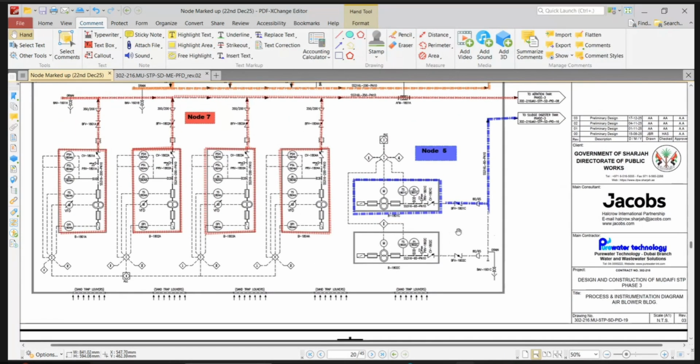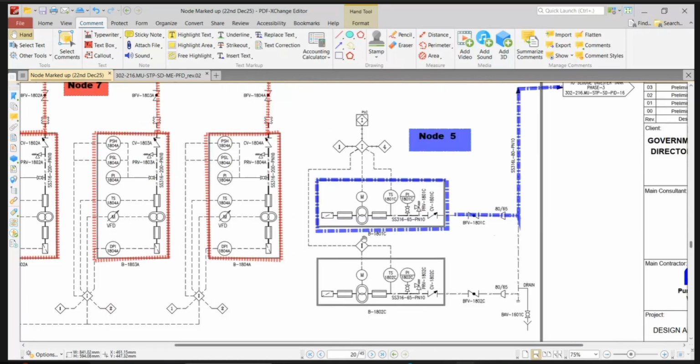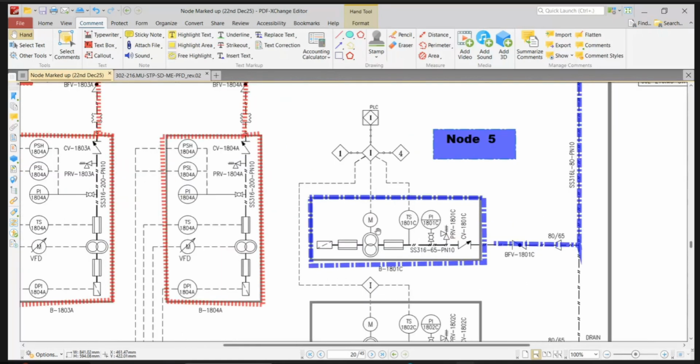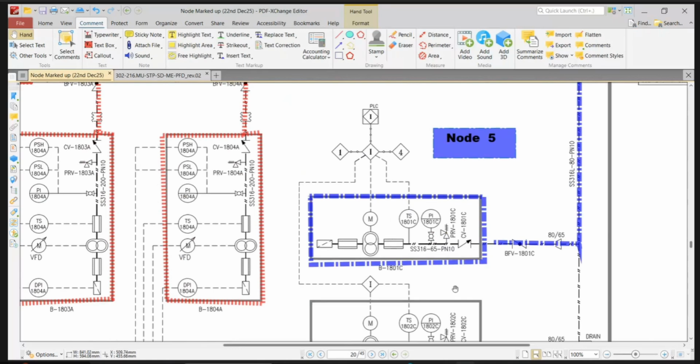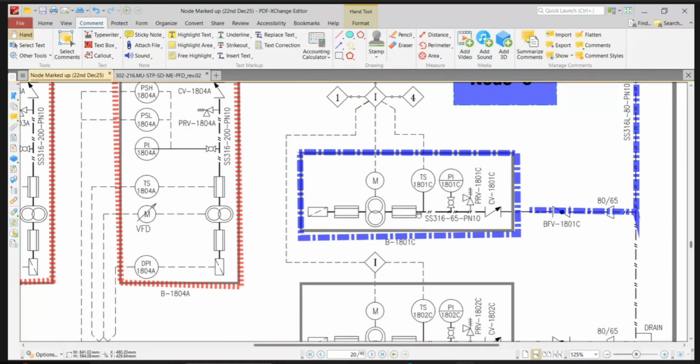Guys, let us focus for 30 minutes. I want to close this node in 30 minutes, then you can take your time to discuss. We are discussing the sludge blower fan, and the configuration is N+1, one running, one standby. So I am going to generate a no-flow situation if the blower fan malfunctions or trips. This is again vendor supply, right? Yeah.